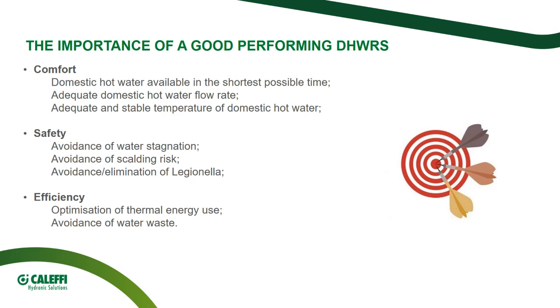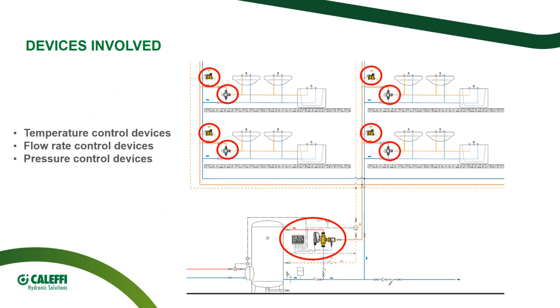The temperature of the water shall be adequate to the use and stable despite the system fluctuation in pressure that may occur. Second aspect to consider is the safety of the users, with particular attention to Legionella bacteria that I have to avoid or eliminate. I also have in these regards to avoid water stagnation throughout the system, but at the same time I have to consider the safety of the users from the scalding risk. All of this has to be achieved with the maximum possible efficiency. So we have to optimize the use of the thermal energy, and we have to avoid as much as we can the water waste.